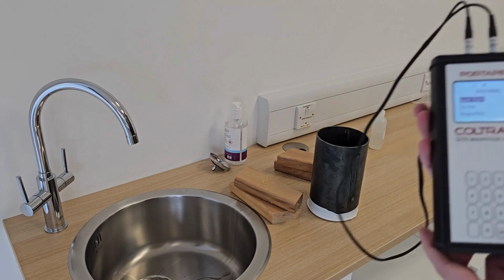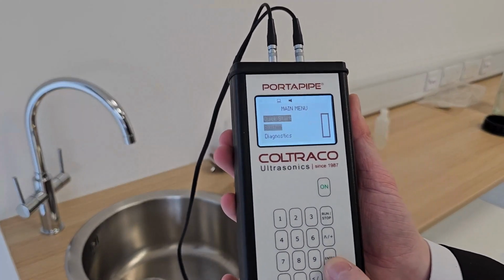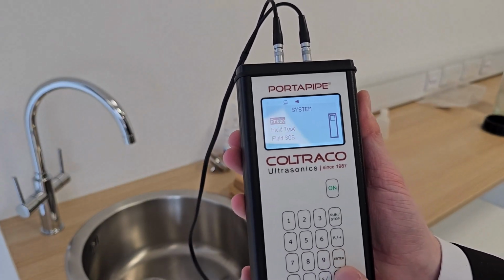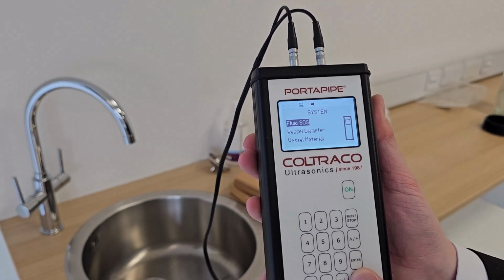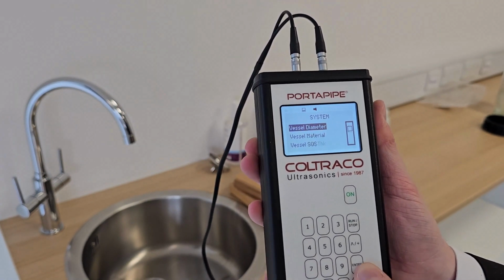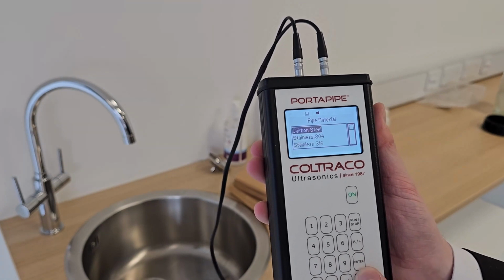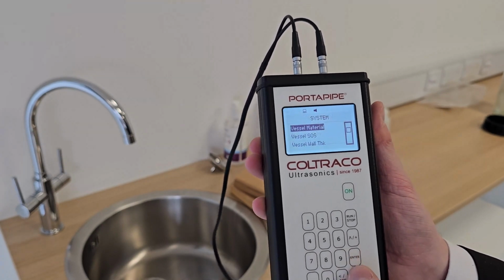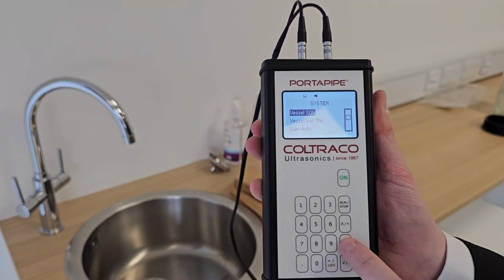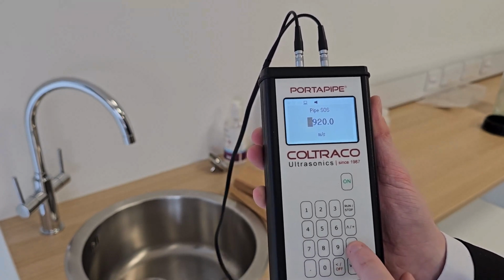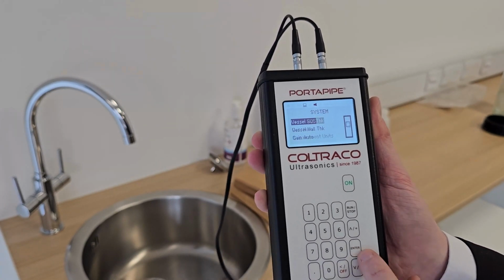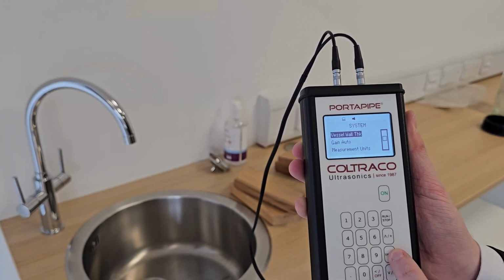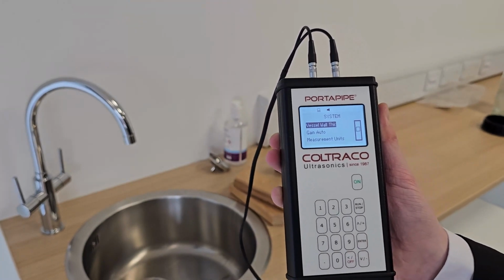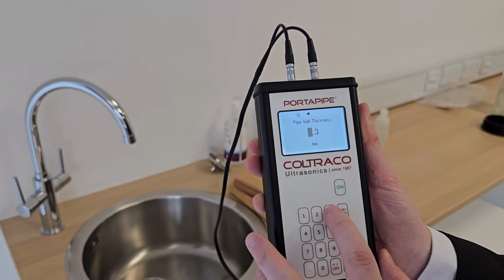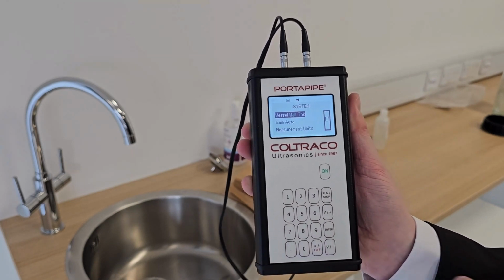Going back into system settings - none of these will have changed, however our vessel material is now carbon steel, so I'll select that. I don't need to change the vessel speed of sound since that's in our database and automatically set. But the vessel wall thickness will have changed slightly - I know these pipes have a 3mm wall thickness, so I'll change that to 3mm.